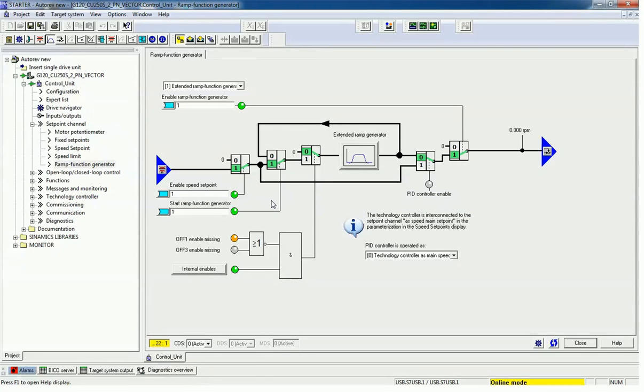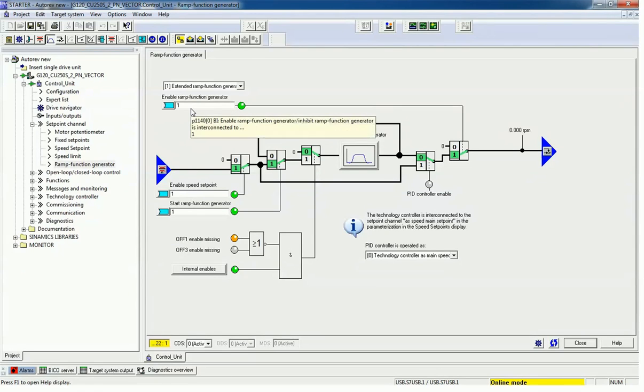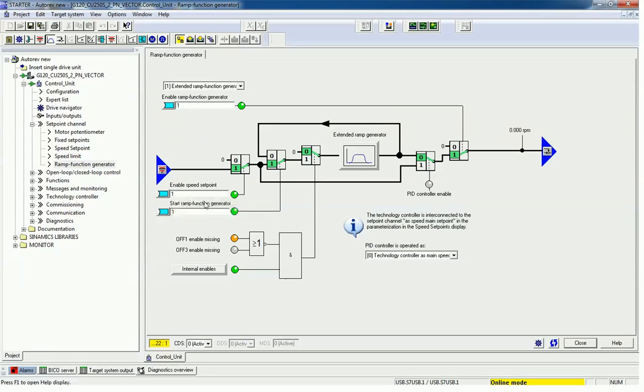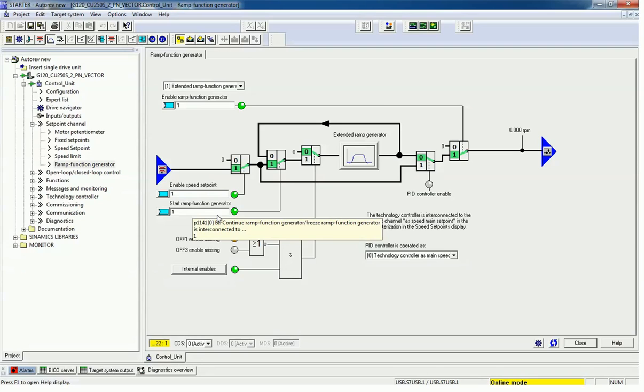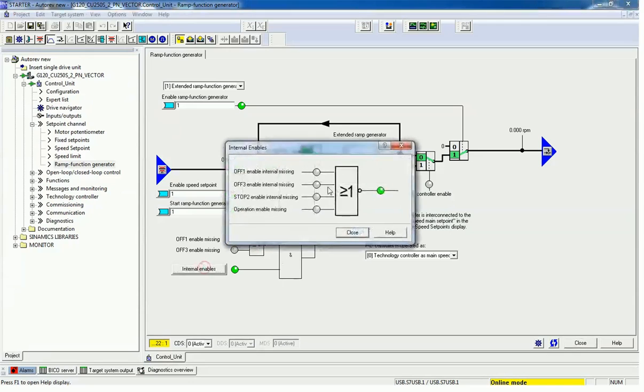Here we get a diagram to configure the ramp function generator. We have already enabled the ramp function generator. You can assign a digital input here — speed setpoint is also enabled, and start for the ramp function generator is also enabled. You can assign any digital input as per your requirement. Downside, we get OFF1 and OFF3 enable, so you can configure any stop method as per your requirement.